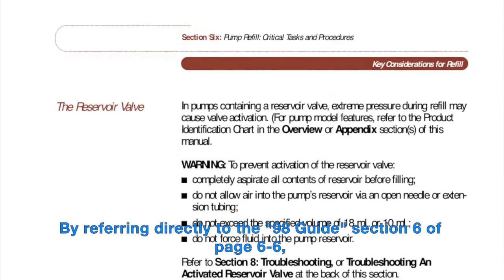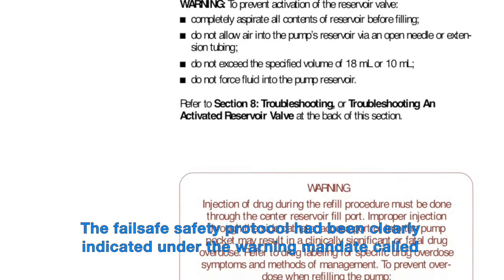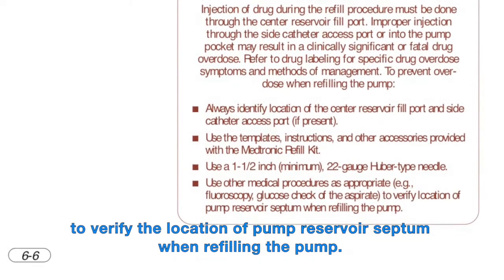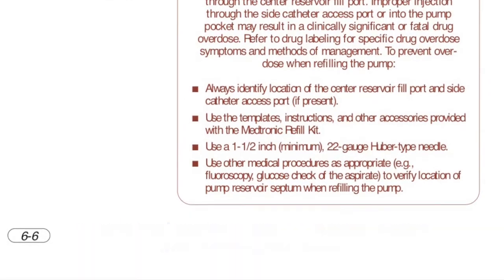Referring directly to the 98 guide, Section 6, page 6-6, the fail-safe safety protocol had been clearly indicated under the warning mandate calling for the use of fluoroscopy procedure, among other things, to verify the location of the pump reservoir septum when refilling the pump.